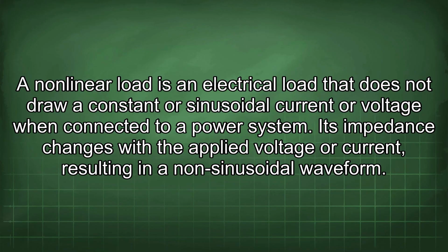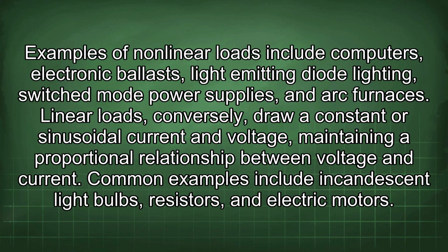A nonlinear load is an electrical load that does not draw a constant or sinusoidal current or voltage when connected to a power system. Its impedance changes with the applied voltage or current, resulting in a non-sinusoidal waveform. Examples of nonlinear loads include computers, electronic ballasts, light-emitting diode lighting, switched-mode power supplies, and arc furnaces.